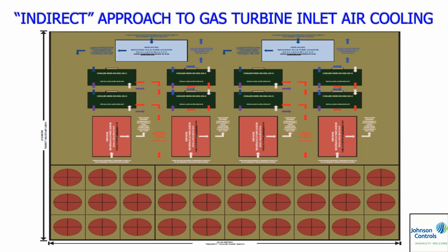So we had a downstream and an upstream evaporator. The upstream evaporator took the flow at X temperature and dropped it down part of the way, and then that temperature entered the second chiller, the downstream chiller, and cooled it the rest of the way. That's what went to the process, or the inlet air coils. On the condenser side, we had those in parallel. What you're seeing here is the blue is chilled water, cold. These are your pumping skids for the evaporator side, and these are your pump skids for the condenser side. Notice we have 8 chillers, 4 skids for the pumps for the condensers, 2 skids for pumps for the evaporator side. These are the fan coolers down here at the bottom.